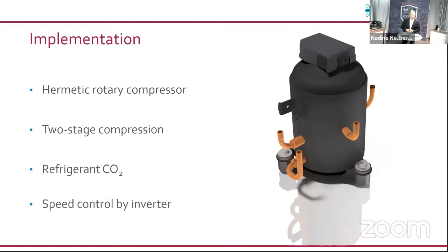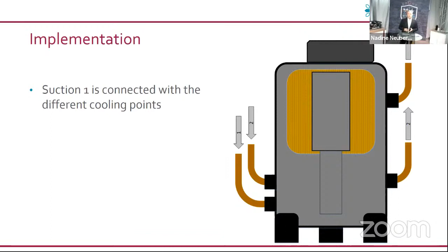Let's talk about the main function of this 2-stage compression. The 2-stage compression of this Panasonic compressor is as follows: the suction line is on the left side. There are 2 suction pipes, and on the right side, there are 2 discharge lines. The first suction line is a typical suction line which comes from the different cooling points of the whole system.